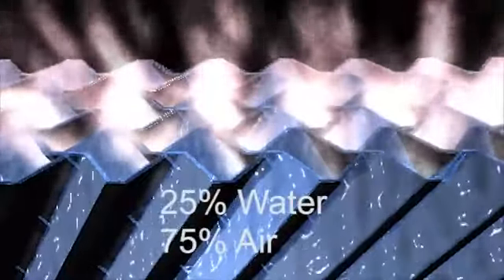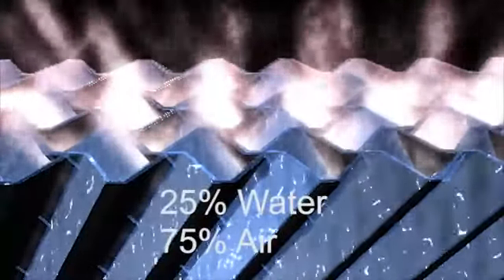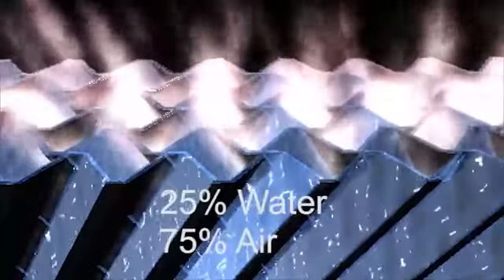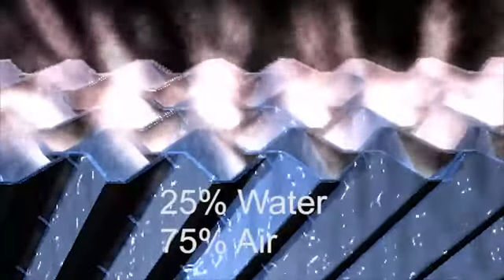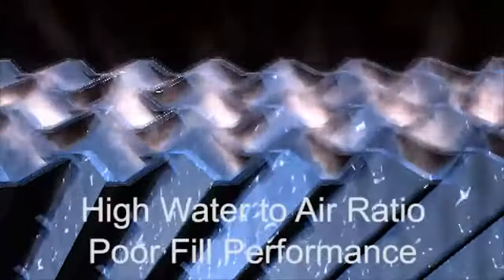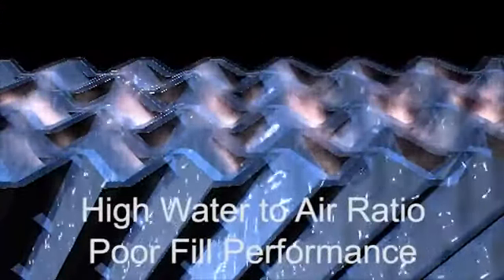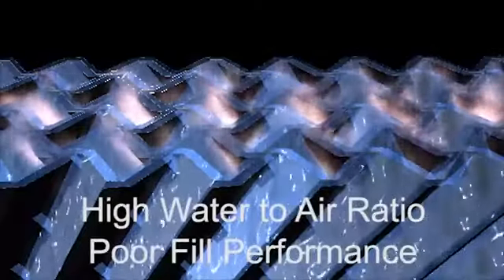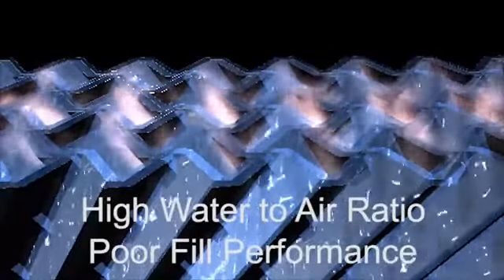Cellular film media consists of a series of corrugated flutes bound together to form a log. Each of these flutes, in essence, becomes a small cooling vessel specifically designed to accommodate 25% of the flute opening being allocated to water loading, and the remaining 75% flute opening dedicated to airflow.